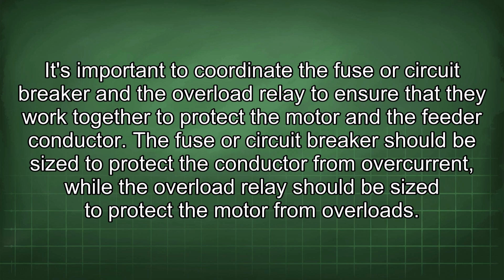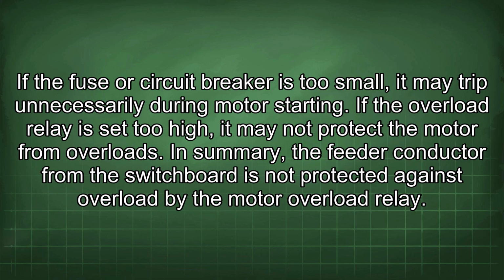The fuse or circuit breaker should be sized to protect the conductor from overcurrent, while the overload relay should be sized to protect the motor from overloads. If the fuse or circuit breaker is too small, it may trip unnecessarily during motor starting. If the overload relay is set too high, it may not protect the motor from overloads.